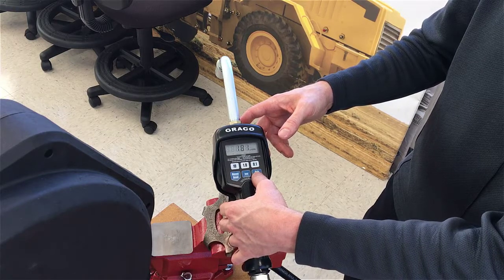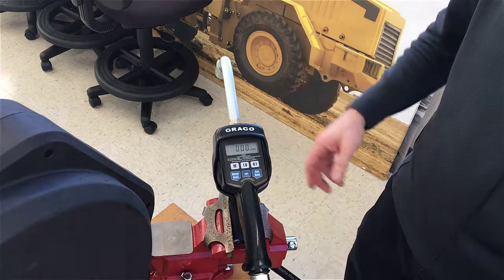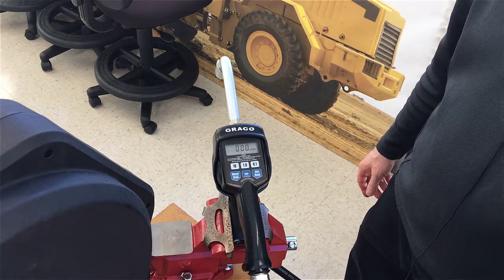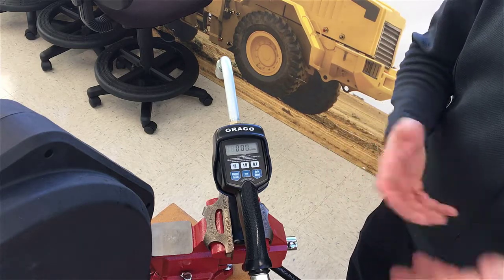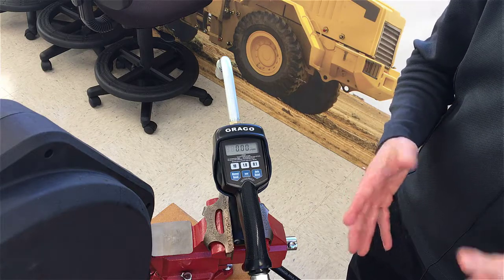Then pass through all the different setup options and now we're ready to dispense as normal — the calibration is complete. If you want, you can also do a confirmation dispense to make sure that whatever we calibrated is exactly one liter.